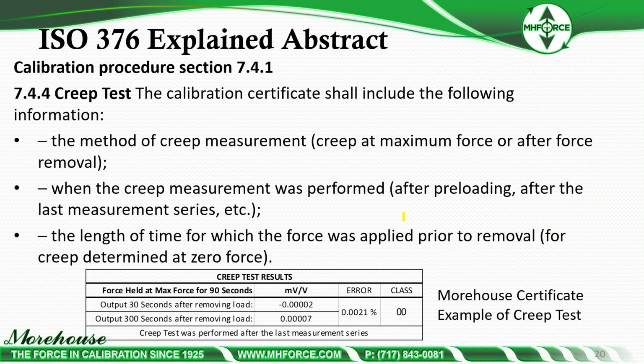So on the certificate, ISO requires the method of creep measurement, creep at maximum force or after force removal. When the creep measurement was performed after preloading, after the last measurement series, the length of time the force was applied prior to removal for creep determination. And then you get down here and you look at our certificate and it says: force held at max force for 90 seconds, output at 30 seconds was negative 0.00002, output after 300 seconds. There's a formula to do this error, class assignment here. And then at the end, lots of labs miss this as well, the requirement to report on the certificate that the creep test was performed after the last measurement series.